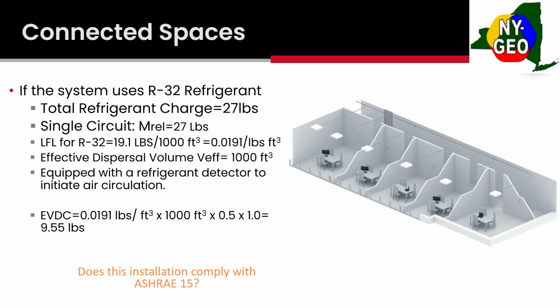So our EVDC is 9.55 pounds. That's how much refrigerant we're allowed to release. This unit has 27 pounds, so it does not meet the requirements. So how do we get around that?